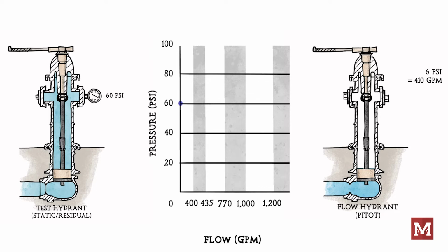Then we open up our flow hydrant with 2 side outlets. Here we measure a pitot pressure of 9 psi with that hydrant that's now fully open. Our residual pressure with this much water flowing comes all the way down to 44 psi. Side note, NFPA 291 suggests that we drop 25% or more from that static pressure. This 44 psi residual pressure would have gotten us there.